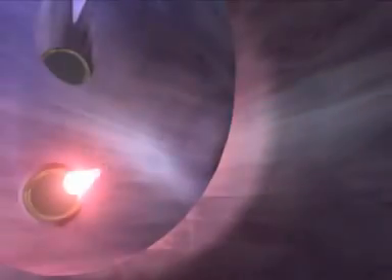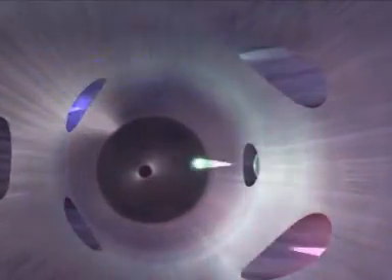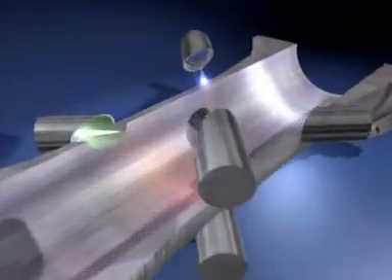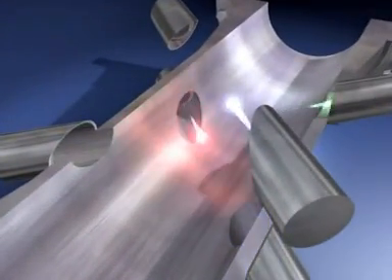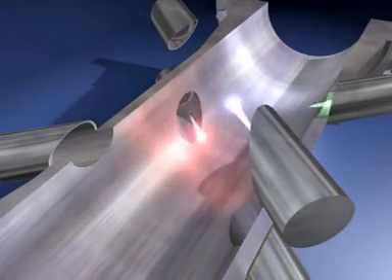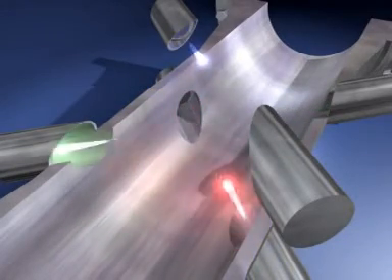The ultrasonic sensors are recessed into the walls of the pipe, so there's virtually no wear and tear. And because nothing protrudes into the pipe, flow rate is unaffected. So there's no pressure drop, no chance of clogging, nor filters needing to be cleaned or replaced. Furthermore, with the Ultrasonic 3, no periodic recalibration is required. Long-term use will have virtually no impact on measurement uncertainty.